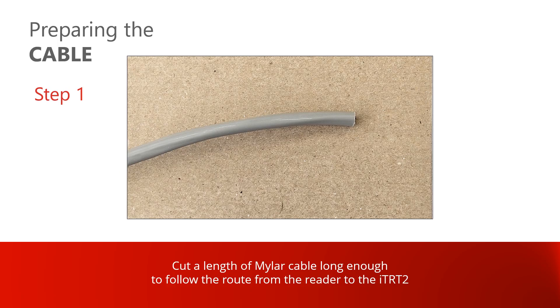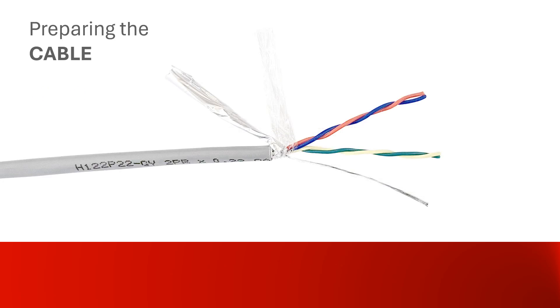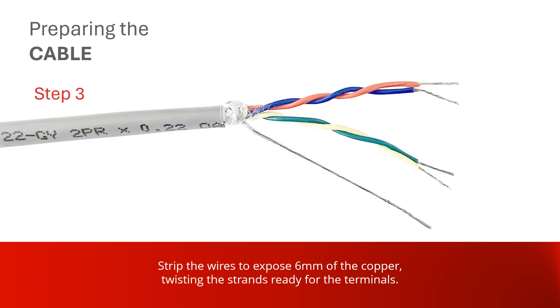Cut a length of Mylar cable long enough to follow the route from the reader to the iTRT2, allowing an extra 30 centimeters to spare. Strip back the outer sheath on both ends by 6 centimeters, then strip all the wires to expose 6 millimeters of the copper, twisting the strands ready for the terminals.